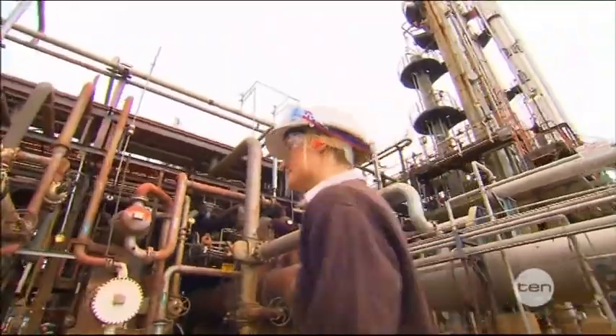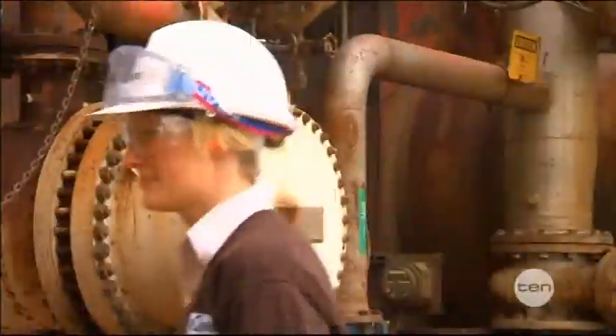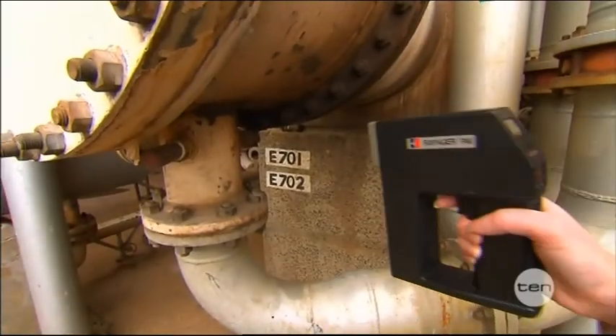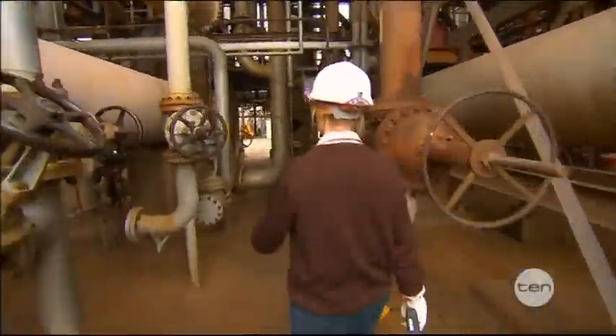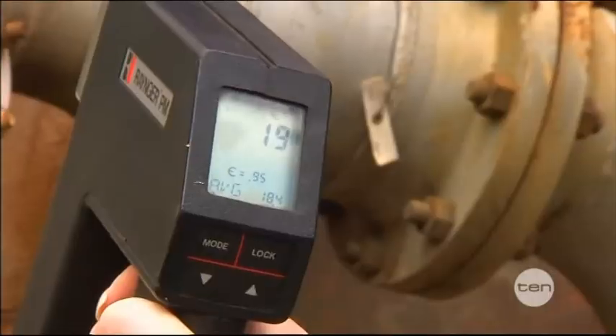So next I head to the plant to see what's going on. I take a thermal imaging camera and an infrared laser gun, and I use them to check the surface temperature of all of the pipes that connect to the two heat exchangers I'm investigating.